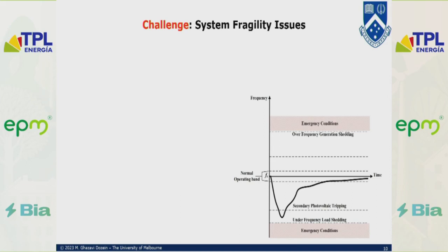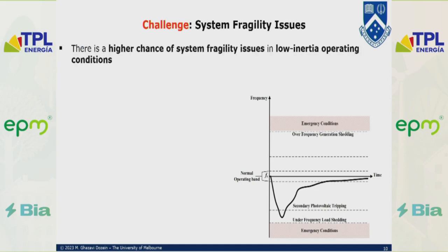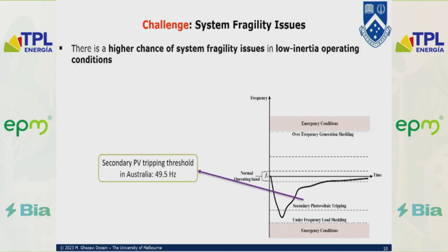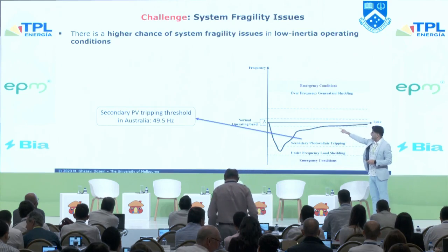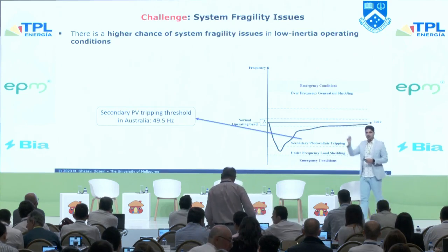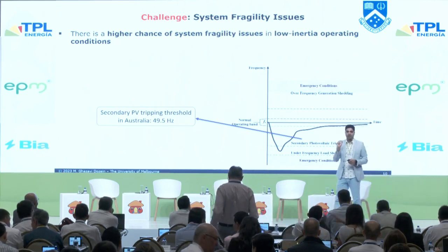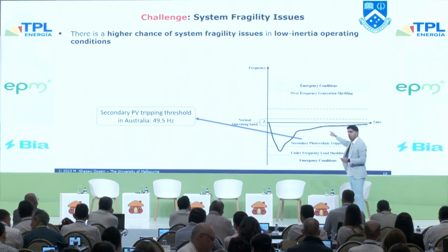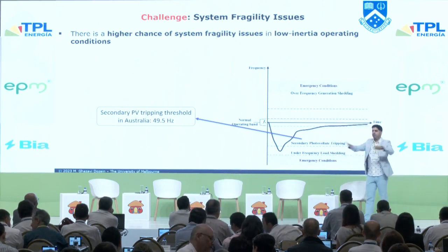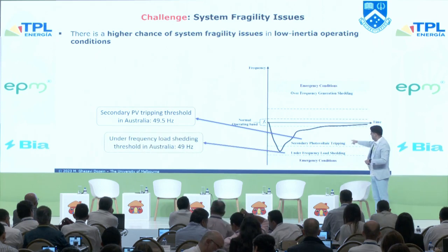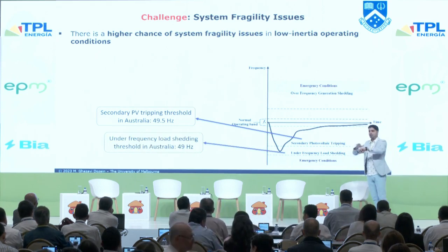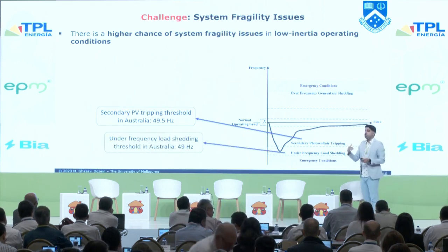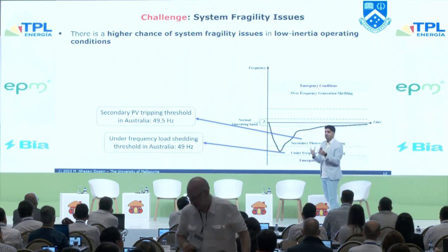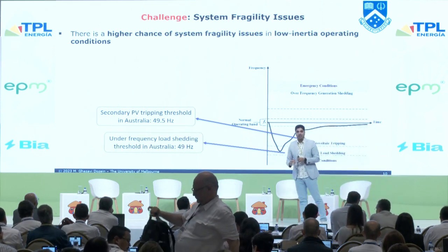Basically, you have frequency-dependent protection schemes in place, such as secondary photovoltaic tripping. In Australia, this threshold is 49.5 hertz, while the nominal frequency is 50 hertz. So if frequency goes below this threshold, PVs would trip, and if frequency goes below 49 hertz, some loads would trip, just to mitigate the active power mismatch created by a contingency.